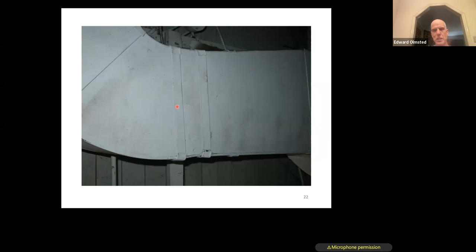A different kind of problem here is condensation. You can sort of see that light coloring, barely visible—that's some visible mold. This is a cooling duct that's not insulated, running through a crawl space that's not air conditioned. So you have hot, humid air in the crawl space, condensation forms on the duct, and they decided to paint it. A duct by itself would be a very low mold growth substrate—mold isn't going to like growing on galvanized or sheet metal. But if you put paint on it, the paint contains latex, which is a protein, and mold will grow on the paint, which it did.